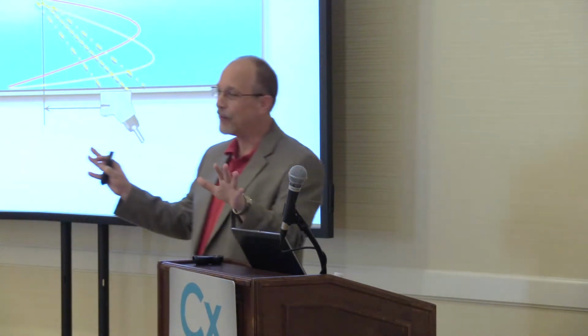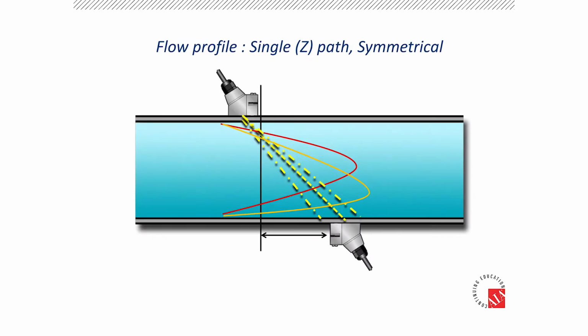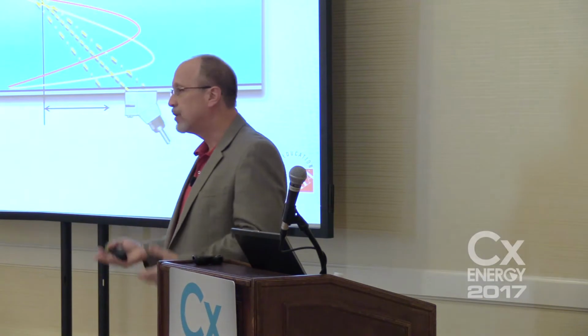That happens all the time. You guys are in the field, you're faced with difficult situations. I don't have enough straight run of pipe. What can I do? If you're point sensing, you can get away with moving the sensor around. If you go a 1/4 inch or 1/2 inch right or left, in most cases the device is rated to be about a 1% device. But many times, when you have to move the sensor, you're no longer at the optimum accuracy specification. If you're not at the optimum accuracy specification, everyone asks, how far could you be off?